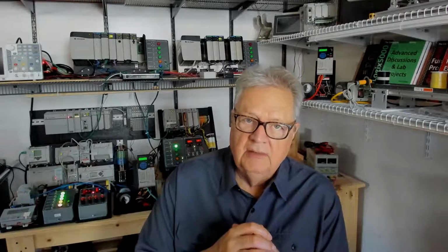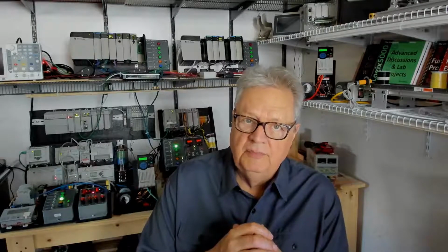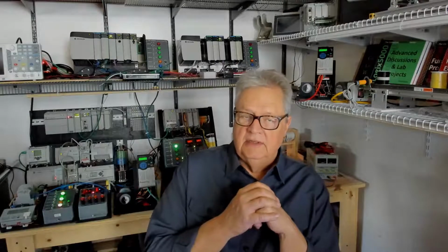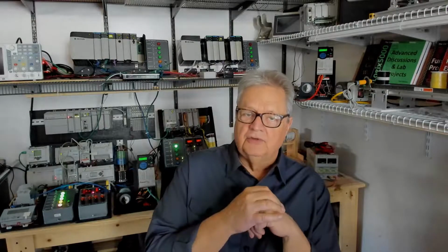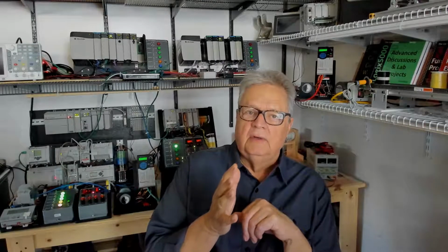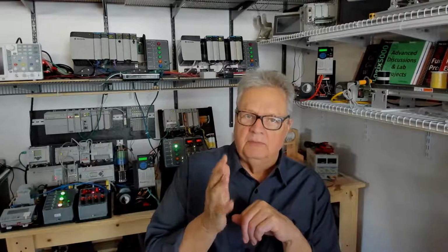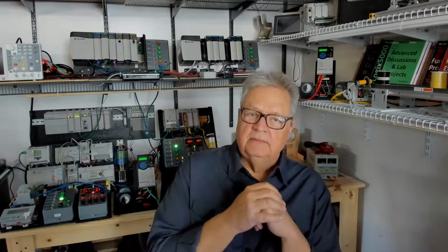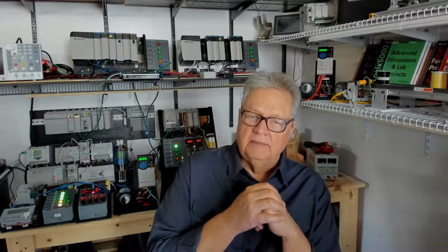If you want to call a Boolean, a BOOL is an atomic data type, but it does take up 32 bits in memory. So it uses one 32-bit DINT, and it uses 1 bit out of those 32 bits for the storage space for that variable, that pointer tag, that's a BOOL data type. So although it uses 32 bits, it's still a single bit. It's a Boolean data type.